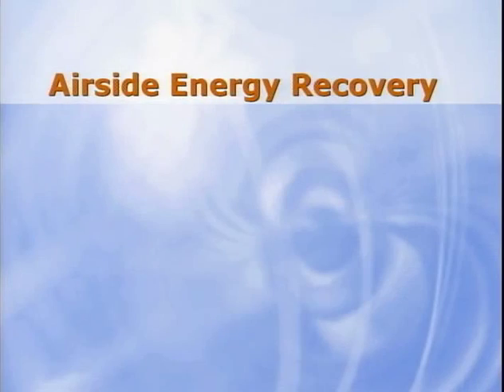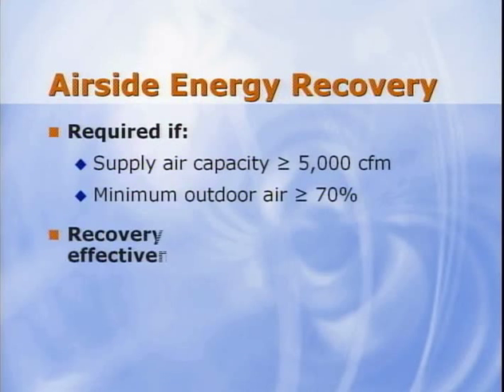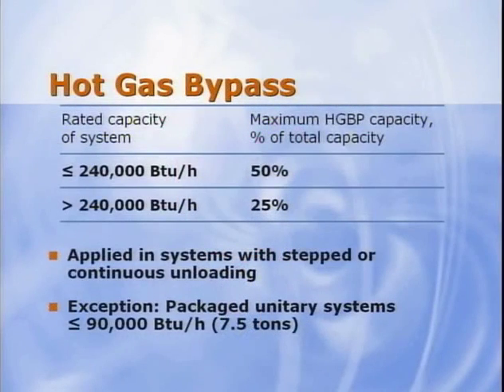Energy recovery with 50% effectiveness is required when individual fan systems have capacities of 5,000 CFM, of which 70% or more is outdoor air. There are 9 exceptions. There's also a limitation on hot gas bypass, not hot gas reheat, but hot gas bypass. As Paul will discuss later, this is very inefficient. The hot gas bypass limitation applies to systems over 7.5 tons, and the limits are shown here.